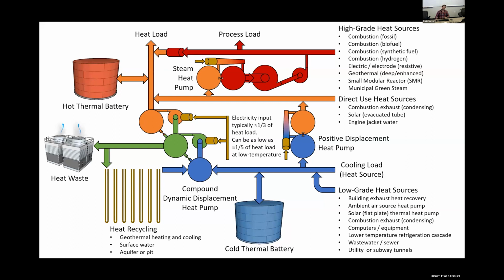We're going to talk more about the heat pumps that are available here. On the left side, we're showing again a compound style of centrifugal heat pump that can either reject heat or recover heat. And then on the right-hand side, we're showing another type of compressor. It's called a positive displacement heat pump. The image is meant to depict a screw, but there's also scroll and reciprocating type compressors. Due to that type of compressor, they're typically dedicated heat pumps or dedicated heat recovery chillers. They wouldn't have to be, but a compound centrifugal is a good way to handle heat rejection or heat recovery, just because of the multiple stages. So it's a little bit more efficient to reject heat with one of those, but you could also use a positive displacement in the same fashion.